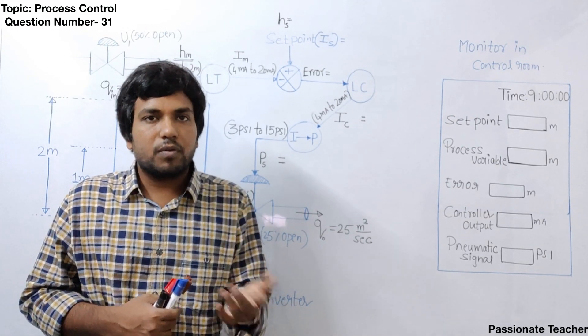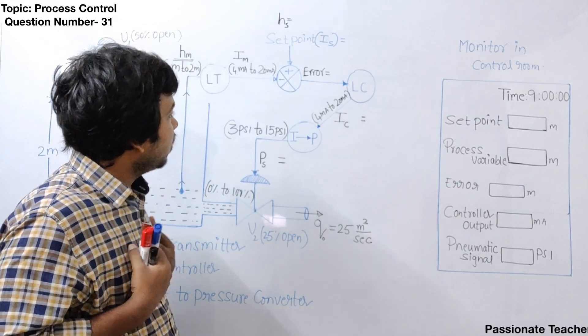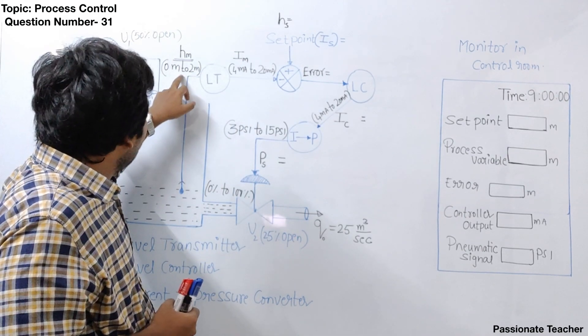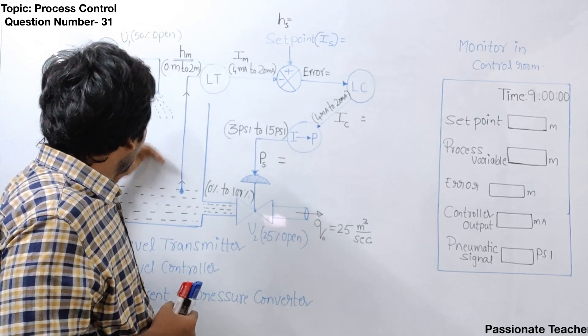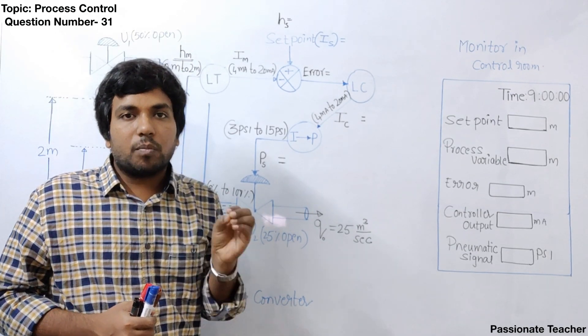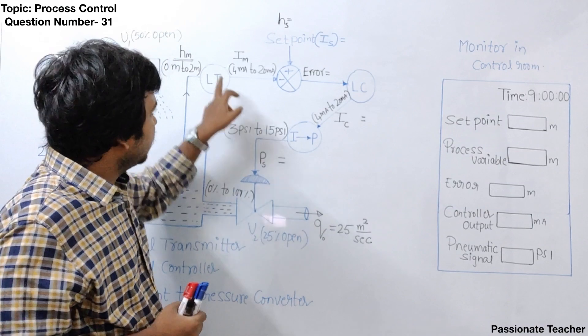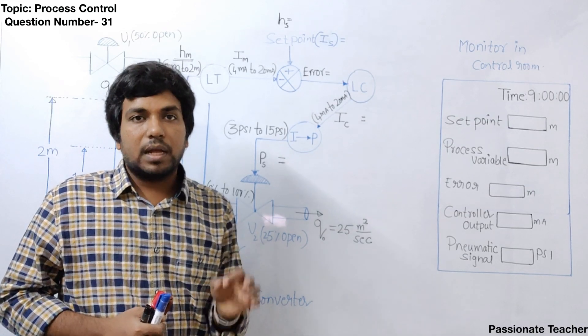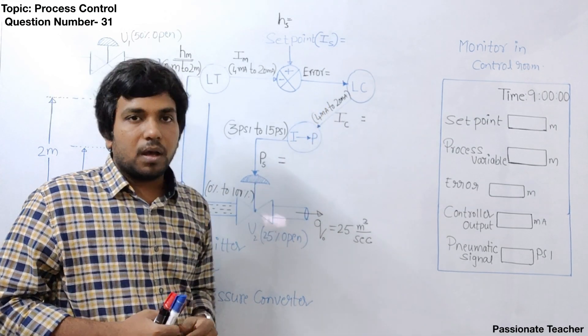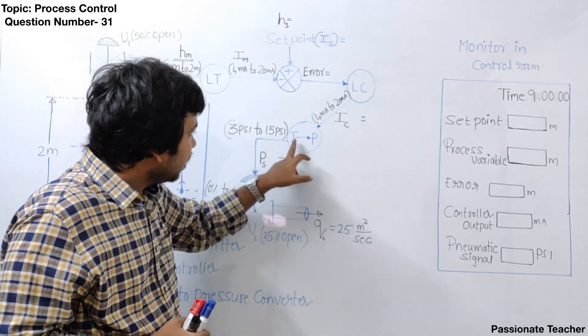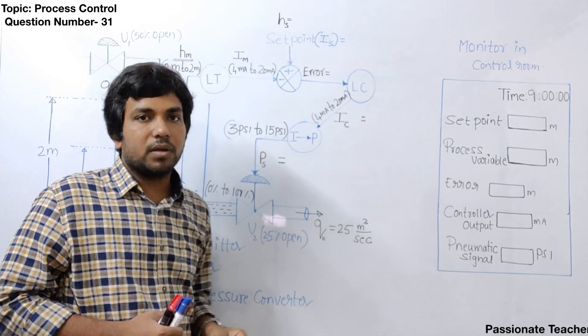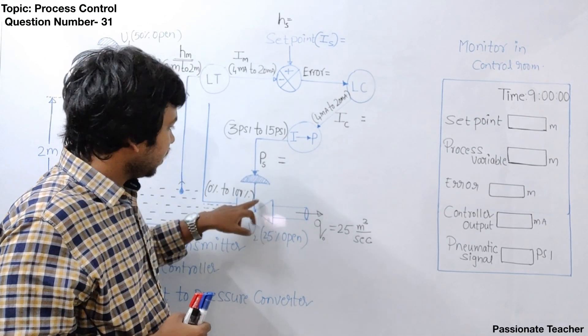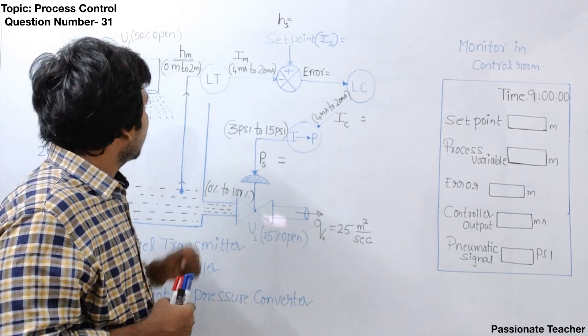Let us look at the variable names used here. The desired water level that we require is called the setpoint. The water level obtained from the process is called the process variable or measured variable. Whatever current we receive from the level controller is called the controller output. Whatever output signal we get after the I2P converter is called the manipulated signal or actuation signal, and that is given to the control valve.